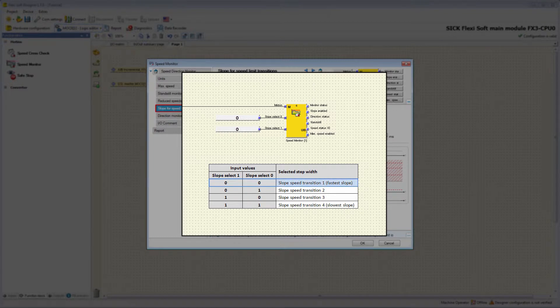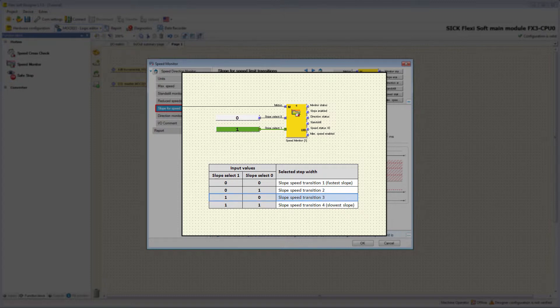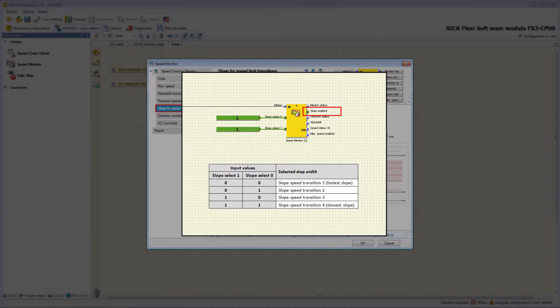The signal combination of SlopeSelect0 and SlopeSelect1 determines which slope is executed. If both inputs are low, Slope 1 is executed. If SlopeSelect0 is high while SlopeSelect1 is low, Slope 2 is performed. To execute Slope 3, SlopeSelect1 must be high and SlopeSelect0 low. Slope 4 is executed if both inputs are high. Regardless of which slope is active, the output SlopeEnabled is high as long as the slope is being executed.